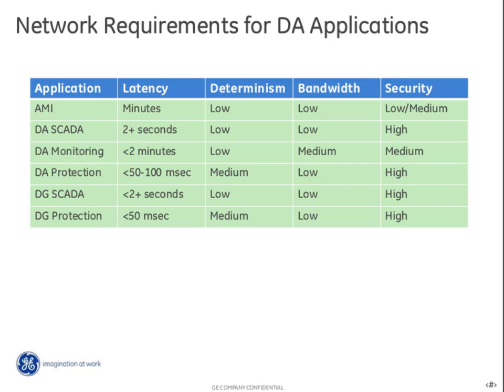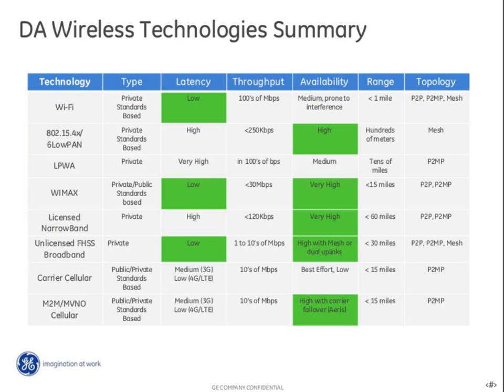Typically, these are a bit more demanding on latency, especially when we're using 61850. And we've seen anywhere between 50 to 100 milliseconds between peer-to-peer controllers, one-way requirement for latencies. Now, for security, pretty much this is very critical as well because, again, somebody hacks on the network, they can log in and flip a recloser open and cut off power on some critical section of the community.